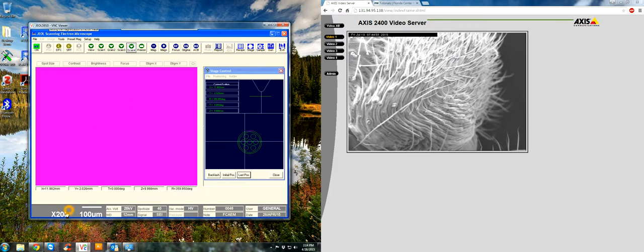Okay, I also like to point out at the bottom of the GUI screen over here, you get your standard information for the SEM: magnification, a scale bar, the accelerating voltage, the working distance, spot size, our signal. We're currently in secondary electron. We're detecting secondary electrons. And we're in high vacuum mode. And all of this can be adjusted depending on what your needs are, what you're imaging. If you're going to high magnification, you want a smaller spot size. If we're looking at environmentally wet or just wet, moist samples, you want to go to low vacuum. If you want better resolution, you want a smaller working distance. So just some of the things that you can change.